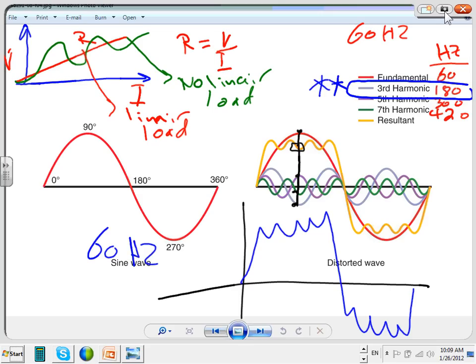Remember how we said to solve the problem of harmonic in the neutral, guys? We either pull a bigger conductor, the phases will be number 12, 12, 12, and the neutral will be number 10. Or we can reduce the amps. So if number 12 can carry 20 amps, we can make it loaded 12 amps by reducing the load, but that will reduce, of course, the current in the neutral. So no matter how you reduce the current in the neutral, you're still not getting a non-burning neutral. Or better off, you pull a neutral with every phase. A neutral with every phase.